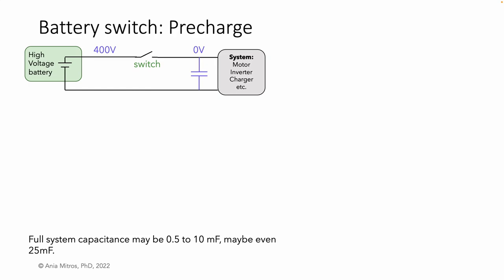On the left, we have the battery; in this example, let's say 400 volts. On the right, we have an unpowered system, so we expect 0 volts. If we simply close the switch, we'll see a very large inrush current. For example, if the big fat bus bars and connectors have a combined impedance of 1/10 of an ohm, we might see an initial current of 4,000 amps. Wowzers! For big systems like home energy storage and cars, this inrush current may be unacceptable.